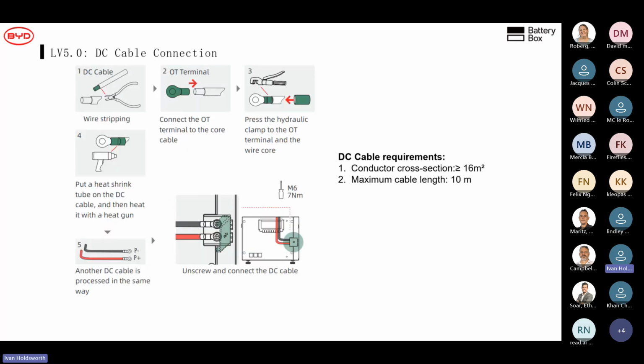For your cables, 16 or 25 square fit quite nicely. With 35 square, sometimes the lugs are too large, and if you screw the 35 square lug in, it might crack the connector. So I recommend 16 or 25. Some 35 squares work, and I have seen people install 50 square and then slice the lugs down to fit. That's not recommended.